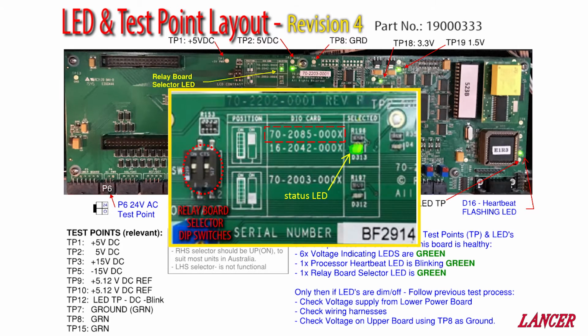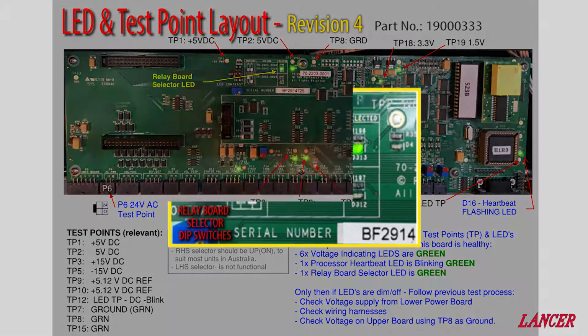With respect to the relay board selector, there is now also 1 LED indicating the current selection. When you install the relay board to the new upper board, check the PCB part number on the relay board and adjust the dip switch to suit, as per the instruction screen printed onto the board. The relays will not operate if set in the incorrect position.